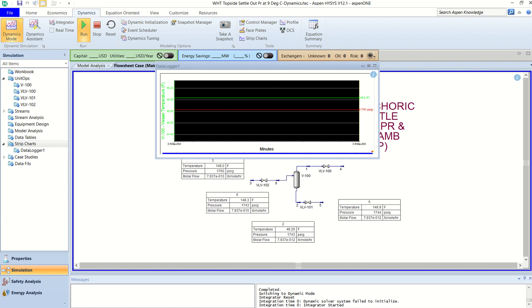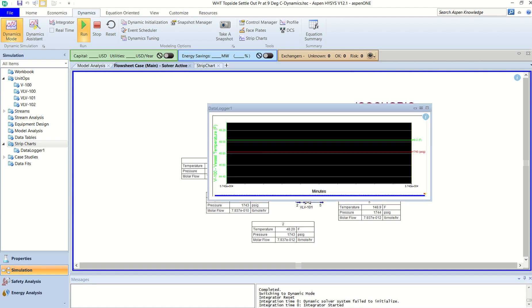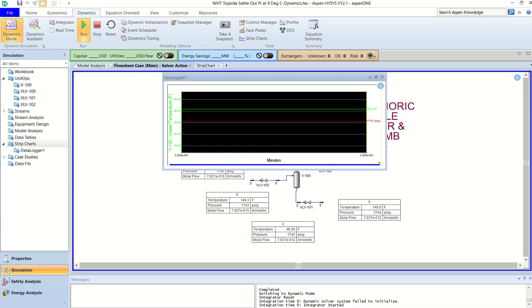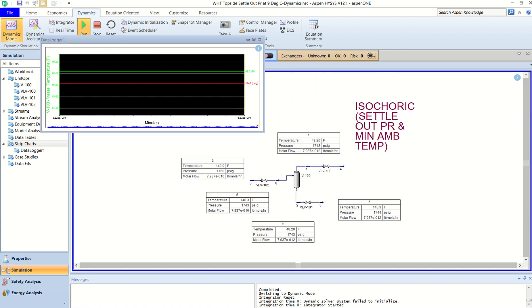So this tells us that given the given volume of the separator, the loss of heat to the ambient and the final temperature, the final pressure is 1743 psig.